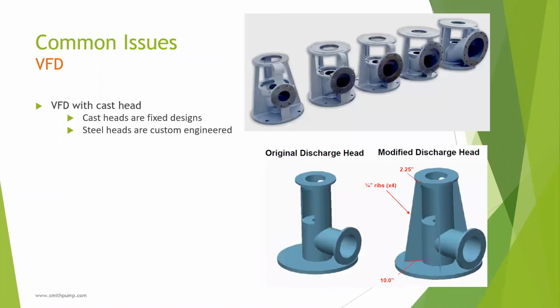Since cast iron heads are a fixed design, they have a fixed natural frequency. Typically, this is okay on constant speed pumps, but it runs a higher risk of vibrating on a VFD as the frequency changes. So how do we combat operating near the natural frequency when slowing down a pump? Basically, a custom fabricated steel head is made for the application.